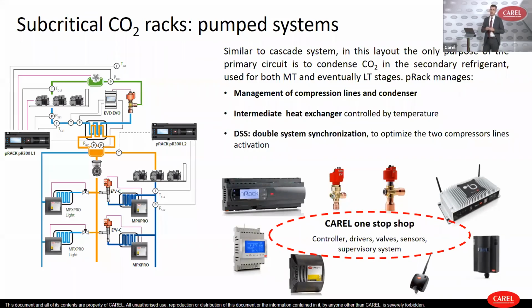So it is synchronizing all the needs of the pumped rack. An important feature that is valid, of course, for the pumped system, but also for the cascade and the transcritical booster system that we will see, is the DSS function that synchronizes the needs of the low temperature compression lines, for example, the one on the right of the secondary circuit, with the line 1 that we use in the primary circuit to condense, how can I say, to keep the CO2 in liquid phase. So for example, if there is a request on the line 2 in the secondary circuit, we activate the line 1 in the primary in order to pre-cool the CO2 and be prepared for this request that is coming from the low temperature side.